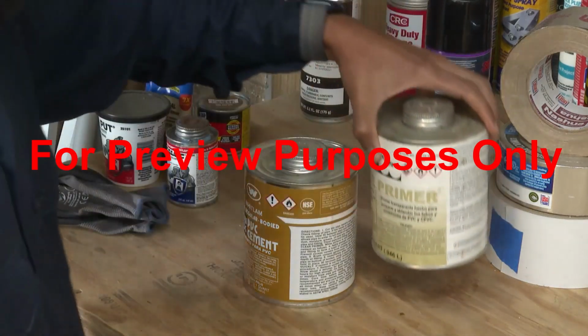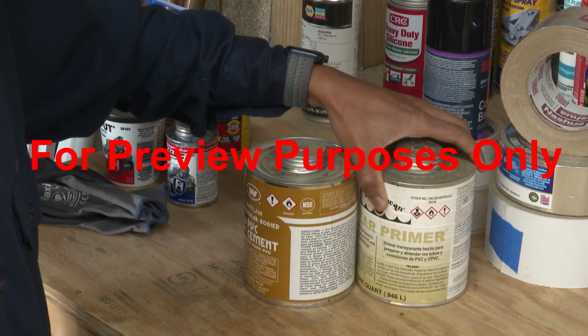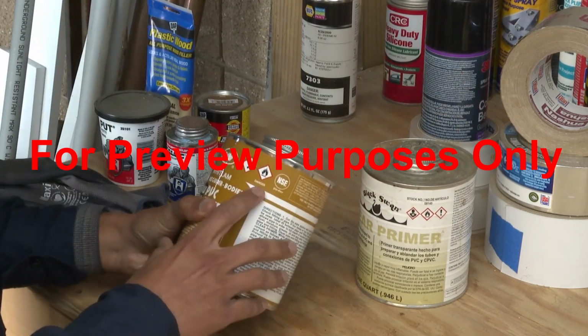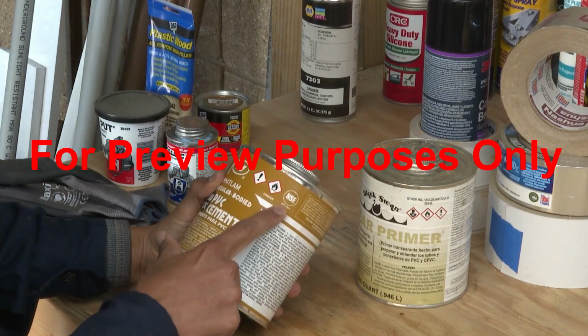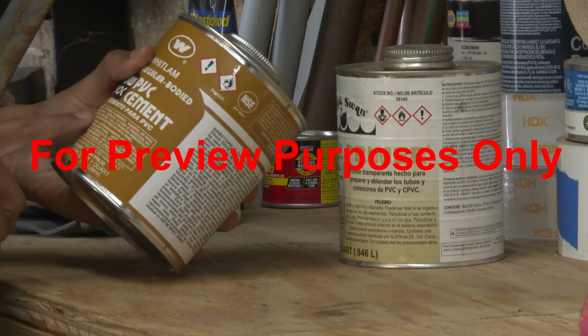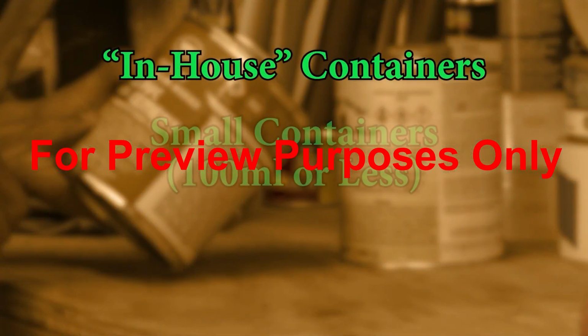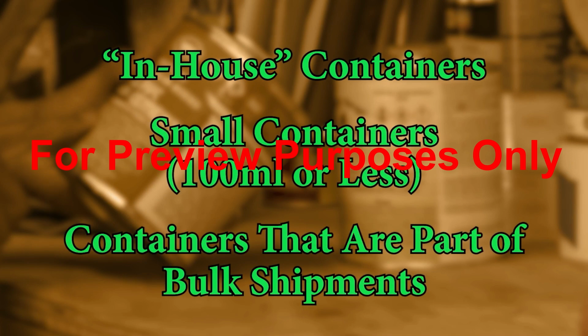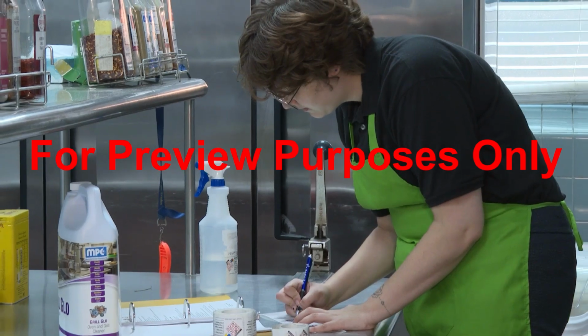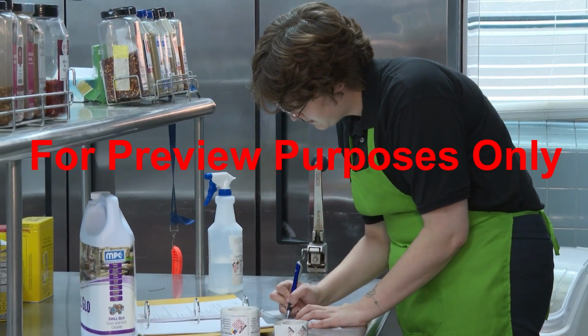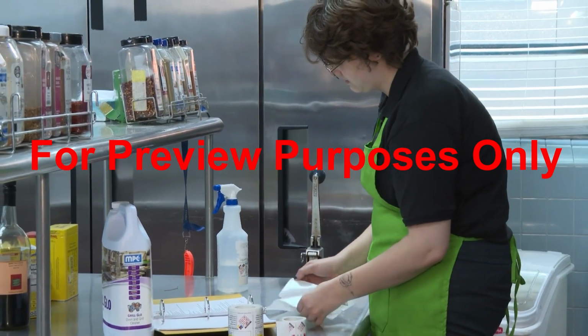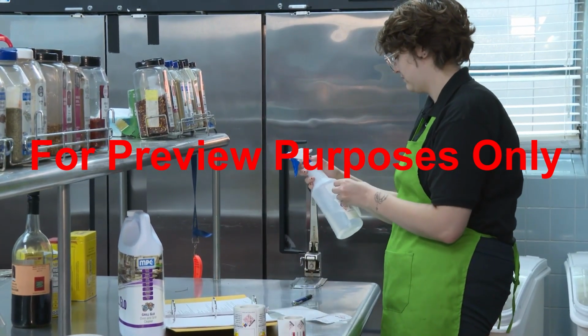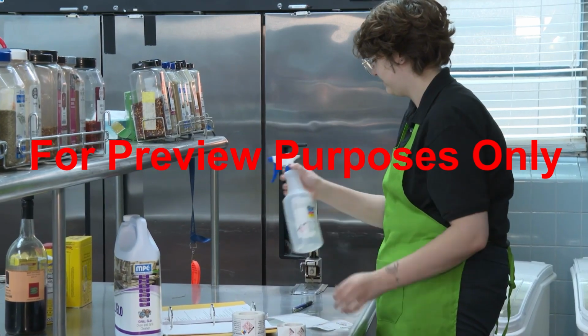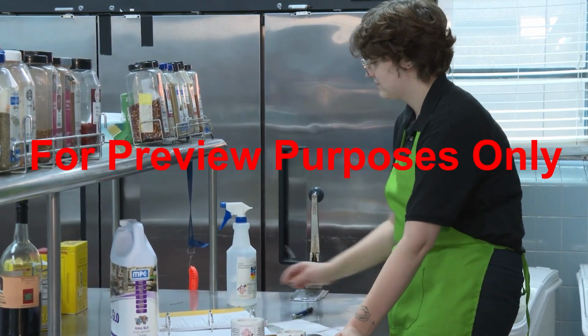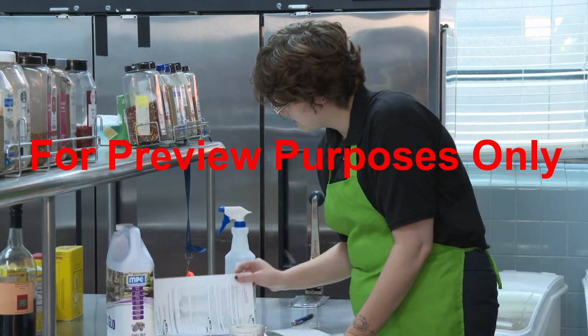Under the Hazard Communication Standard, GHS compliant labels must be displayed on almost all hazmat containers, but there are some unique considerations for in-house containers, small containers, 100 milliliters or less, and containers that are part of bulk shipments. In-house containers are secondary containers that will never leave a facility. While in-house labels do not have to follow the GHS format, they do have to display all of the information that is required by the system.